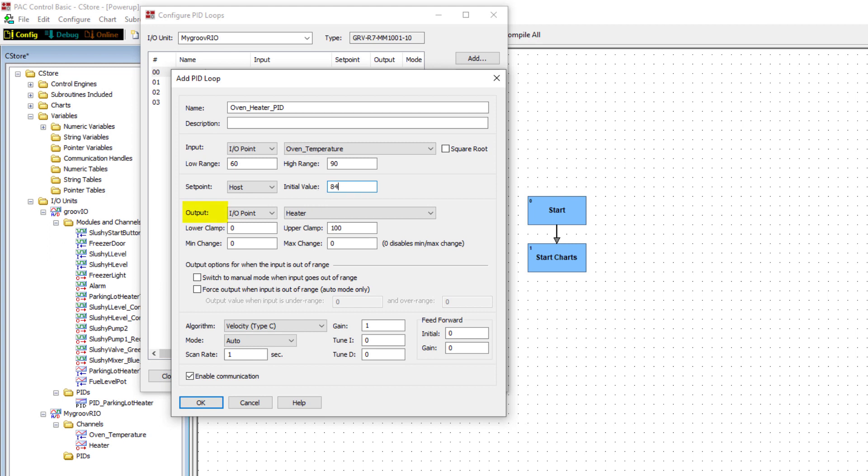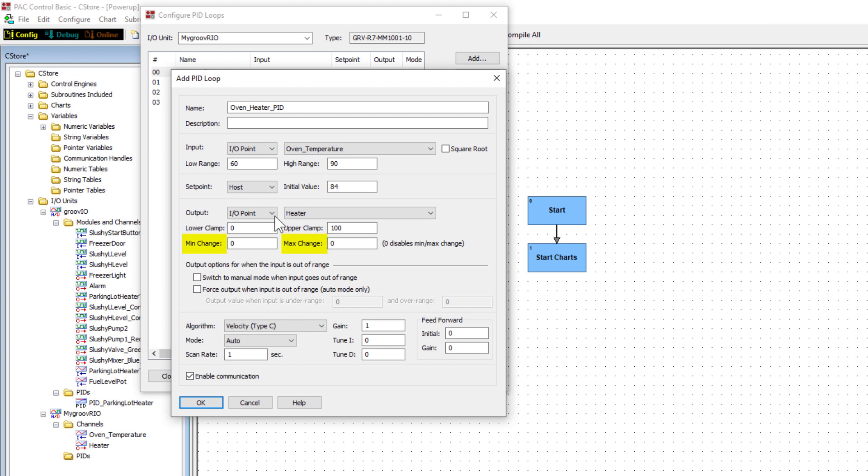The output options are I.O. point or host. Choose I.O. point to select the analog output point we configured. Lower clamp and upper clamp, be sure to set a valid clamp range. This prevents the output from going below or above the limits you've set. Set the upper clamp to 100. Min and max change are optional. Min change refers to what the minimum change should be before the output reacts to the change. Max change is the maximum amount of change allowed by the output. This can prevent drastic changes that could damage your devices. Leaving the values at zero disables them.